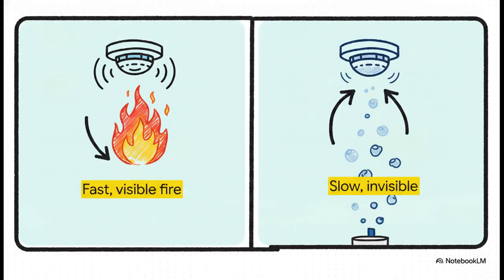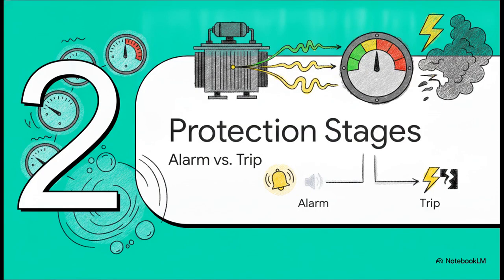Now, people sometimes treat this mechanical protection as just a backup to the fancy electrical differential relays, but no, they cover genuinely different failure modes. Think of electrical protection as the smoke detector in your house. It catches fast, visible fire events instantly. The Buchholz relay, that is your carbon monoxide detector. It catches the slow, invisible danger building up over time that your smoke detector would never notice until it's way too late.